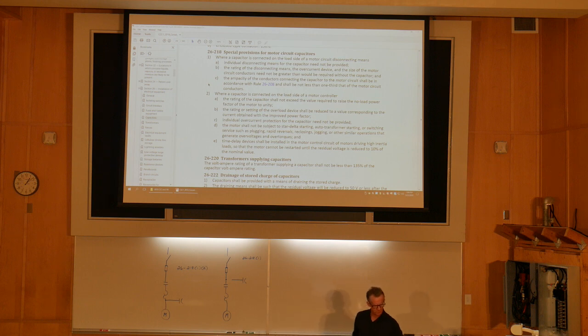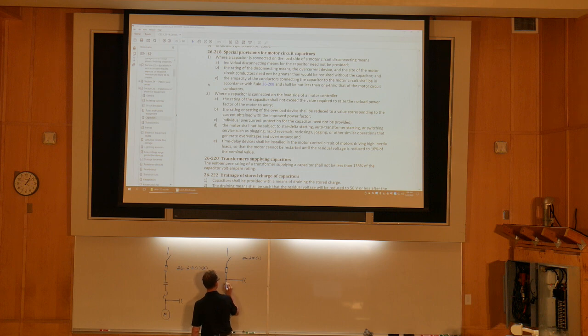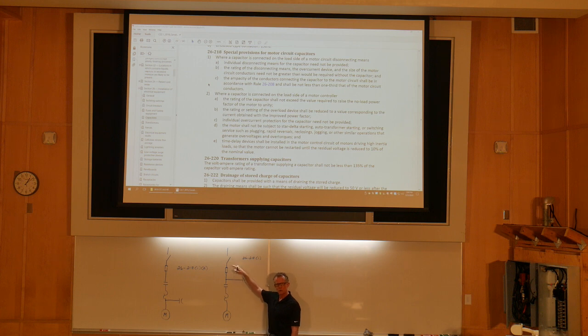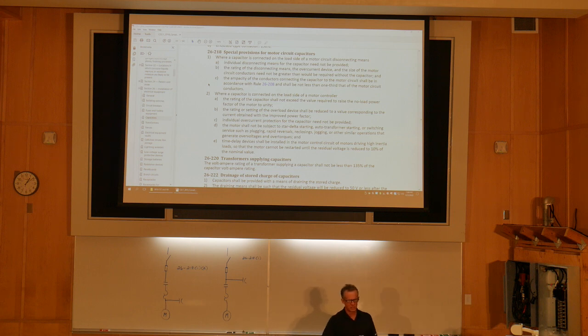You don't change anything. Then, when I do connect the capacitor up, these conductors have to be at least 1/3 that of the motor branch circuit conductors. All right? That's subrule 1A, B, and C. So it applies here, and it applies here. Then subrule 2. Where a capacitor is connected on the load side of the motor controller. So this is what you've got to be aware of. They're on the load side of the overloads.